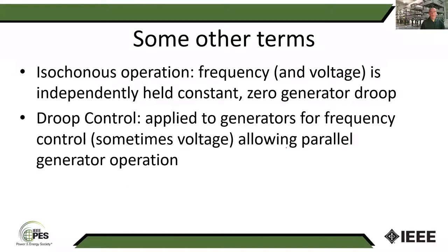And so some terms that go with grid forming operation is people will refer to isochronous operation. And so now frequency and possibly voltage magnitude is independently held constant. You may not have any sort of frequency droop or voltage droop, or you may have a frequency droop more looking like a synchronous machine. If you have more than one generator operating in parallel, then it's going to be more important to have some sort of a frequency droop so that they can share the load between them, which is similar to what you see with conventional synchronous machines, and they already have an inherent natural frequency droop.